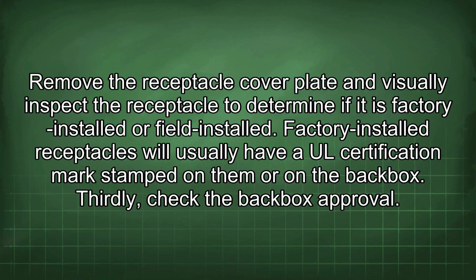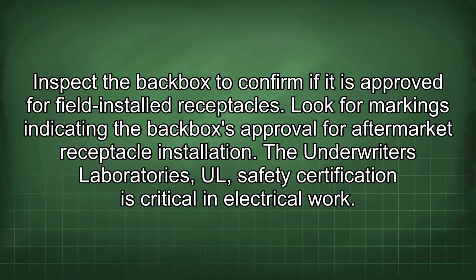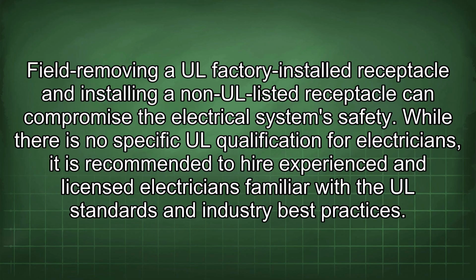Thirdly, check the backbox approval. Inspect the backbox to confirm if it is approved for field installed receptacles. Look for markings indicating the backbox's approval for aftermarket receptacle installation. The Underwriters Laboratories UL safety certification is critical in electrical work. Field removing a UL factory installed receptacle and installing a non-UL listed receptacle can compromise the electrical system safety.